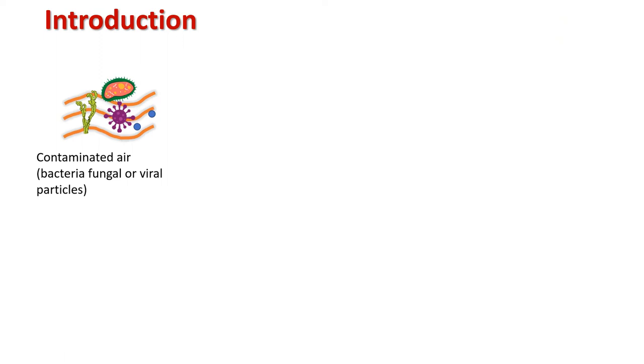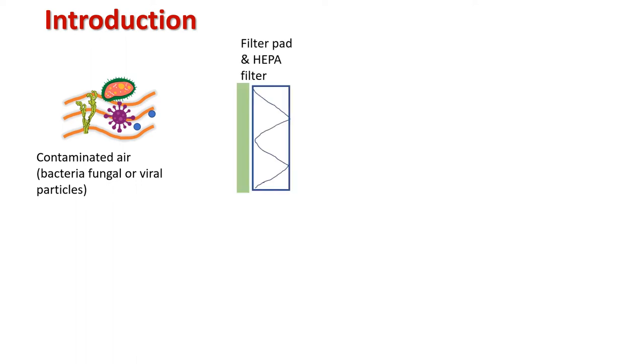Air entering this cabinet may contain biological contaminants like bacteria, viruses, fungal parts, spores, and other impurities such as dust. Filters present in LAF remove all these biological contaminants and impurities. Laminar airflow filters can remove particles that are up to 0.3 micron in size.